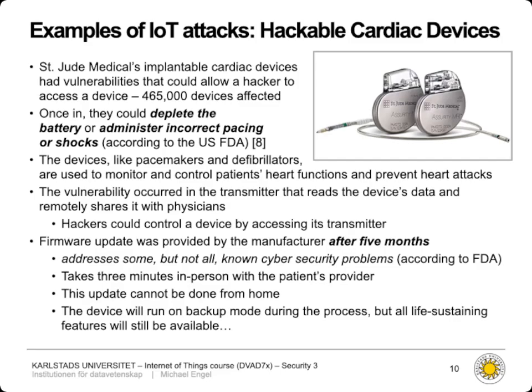And the firmware upgrade, as far as the internet says, was only provided by the manufacturer after 5 months. And still, this addressed only some but not all of the known cybersecurity problems of these devices. Even worse, this update is fast. It takes only 3 minutes in person with the patient's provider of the devices, but you cannot do it from home. So these devices have to be taken into a, well, service station, in this case, a physician, and then this software has to be updated.